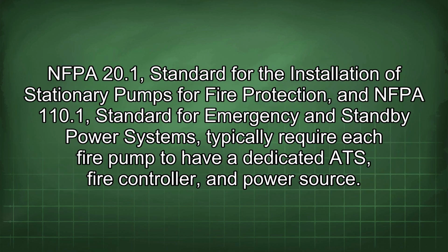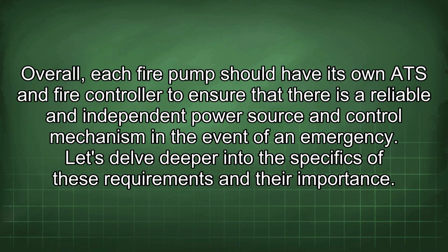NFPA 20.1 standard for the installation of stationary pumps for fire protection, and NFPA 110.1 standard for emergency and standby power systems typically require each fire pump to have a dedicated ATS, fire controller, and power source. Overall, each fire pump should have its own ATS and fire controller to ensure that there is a reliable and independent power source and control mechanism in the event of an emergency. Let's delve deeper into the specifics of these requirements and their importance.